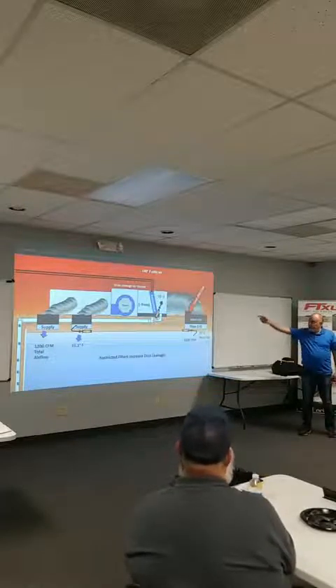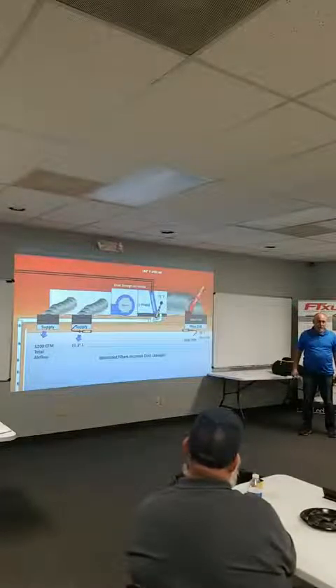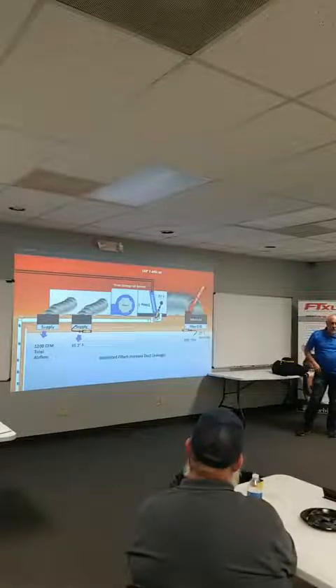You can measure what was coming into the return, it was 70 degrees, and figured out you had 200 CFM leakage into the return air duct. You realize that turning that blower speed down isn't fixing the damn problem. You just got the split right, but now you haven't taken care of the duct leakage, right? This is a very common problem in our industry. So Measurequick will actually pick up that duct leakage. And this could be the same thing if you have an economizer leakage. Doesn't matter, right? It's the exact same thing.